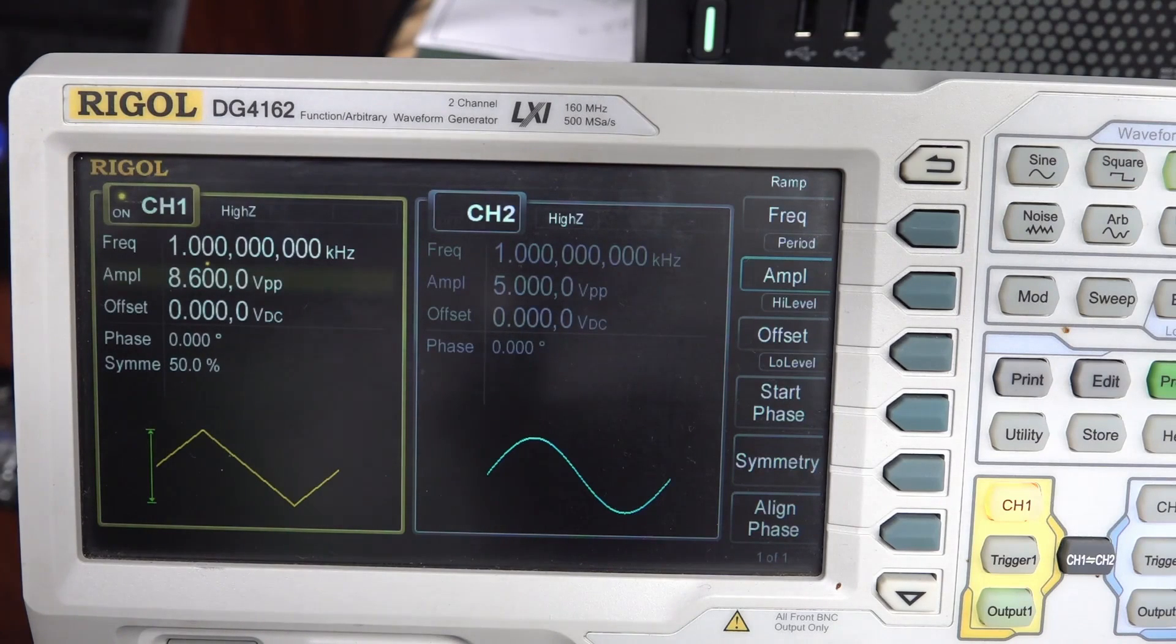But anyway, that's how you measure the, in theory, the ADC dynamic range of a scope. Just put in a triangle wave, it's easy, and just see when it clips. So I hope you found that useful. If you did, give it a big thumbs up. As always, discuss down below, and I'll link to the EEVblog forum thread where people are discussing, measuring, comparing the noise floor of this thing. Catch you next time.